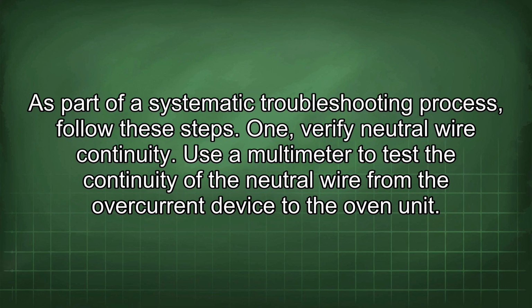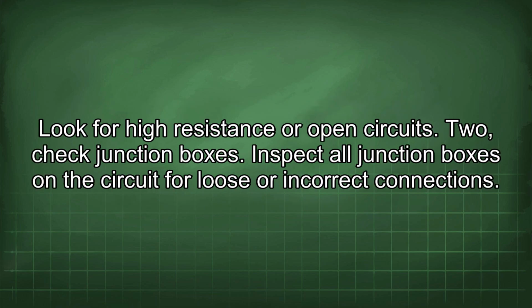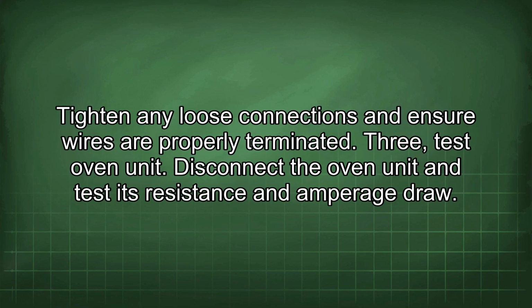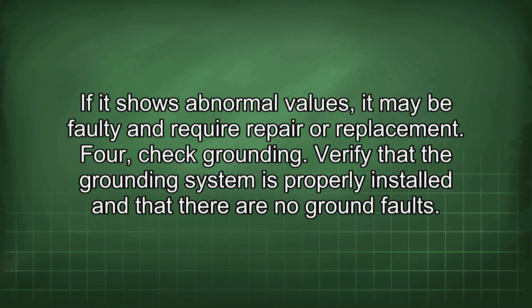1. Verify neutral wire continuity. Use a multimeter to test the continuity of the neutral wire from the overcurrent device to the oven unit. Look for high resistance or open circuits. 2. Check junction boxes. Inspect all junction boxes on the circuit for loose or incorrect connections. Tighten any loose connections and ensure wires are properly terminated. 3. Test oven unit. Disconnect the oven unit and test its resistance and amperage draw. If it shows abnormal values, it may be faulty and require repair or replacement.